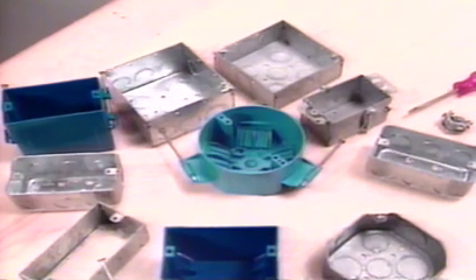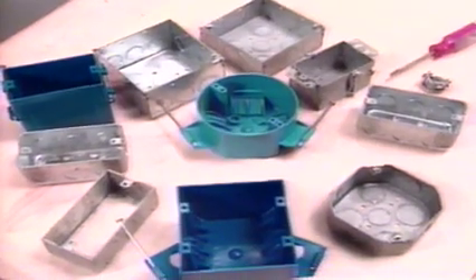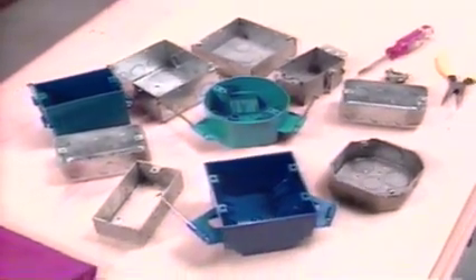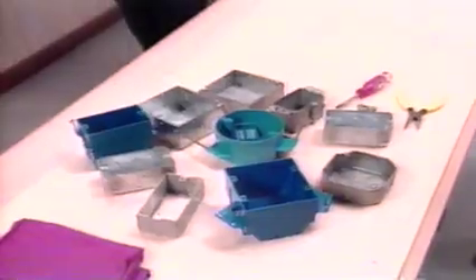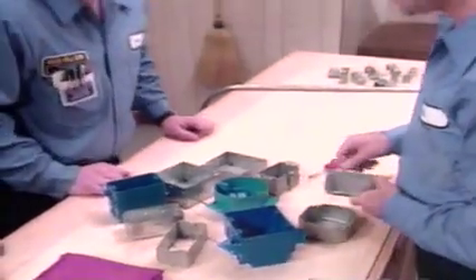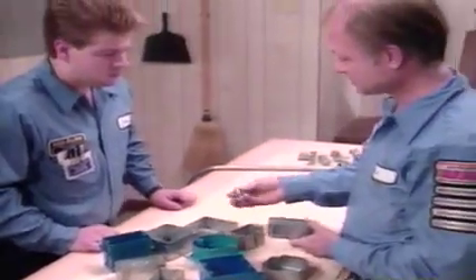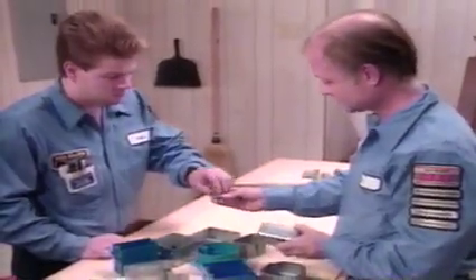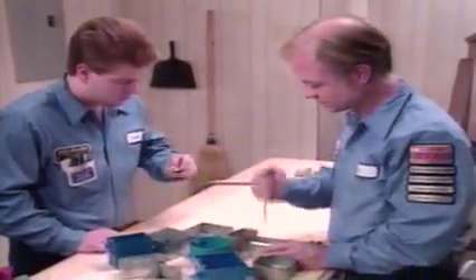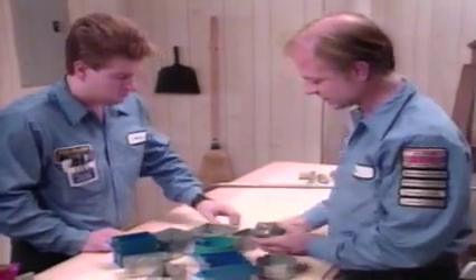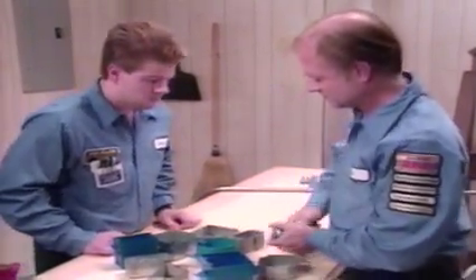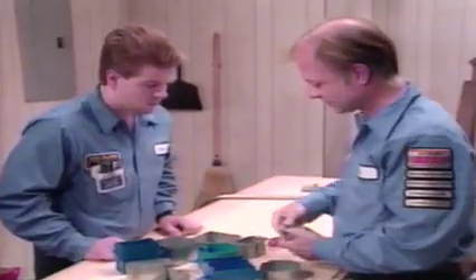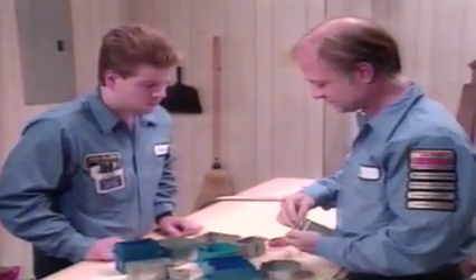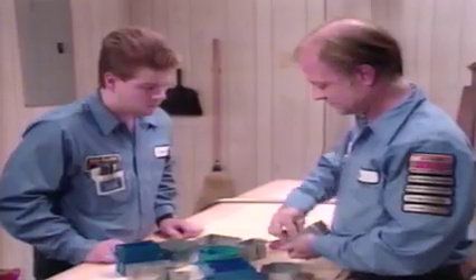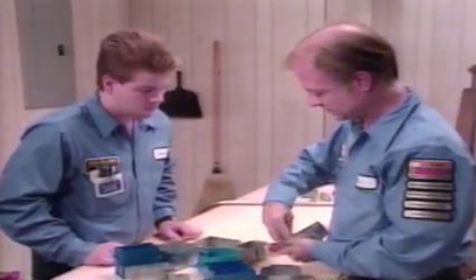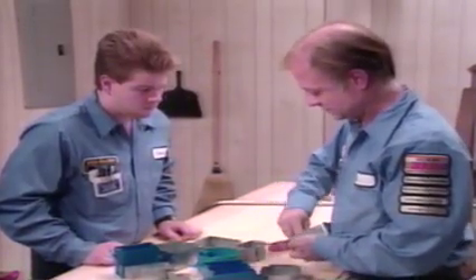Junction boxes are used where wire connections are made. These boxes are available in different depths depending on the number of connections that will be contained within the box. A chart in your workbook shows the maximum number of connections permitted by the NEC, according to the wire size and the box depth. When working with electrical boxes, junction or J boxes, you must punch out a knockout for each cable that will be entering the box. Use a screwdriver and, if needed, a hammer to do this.